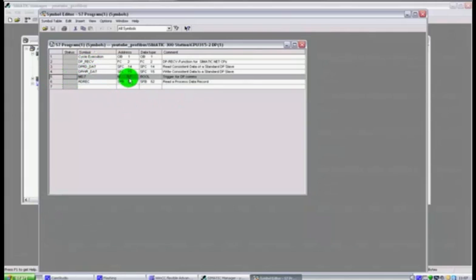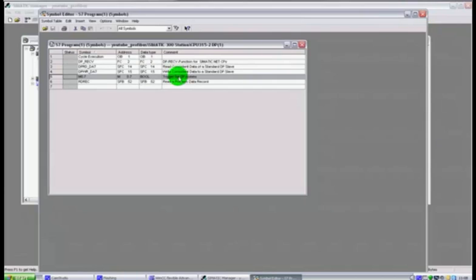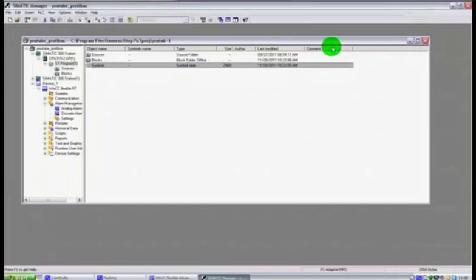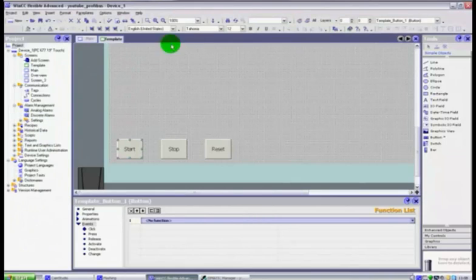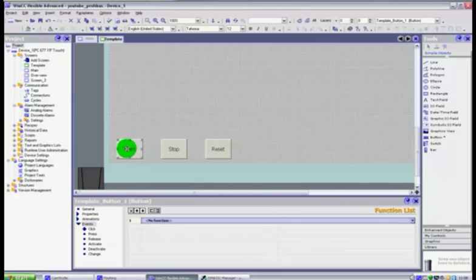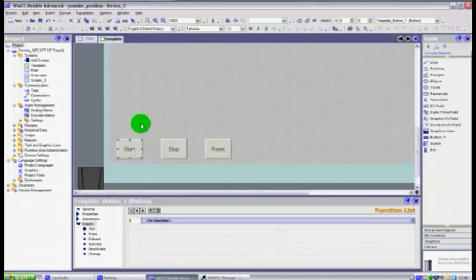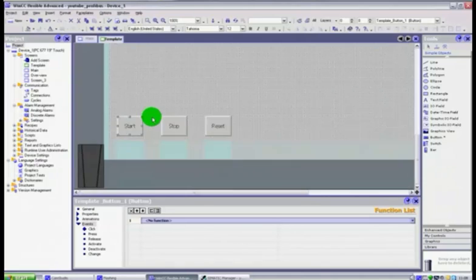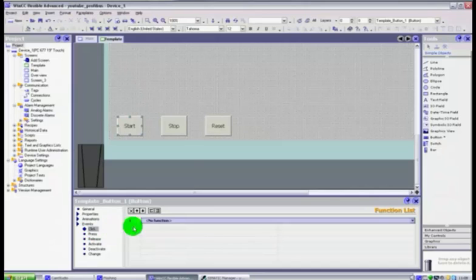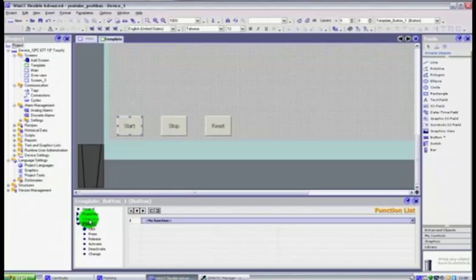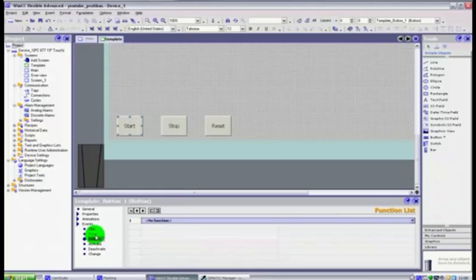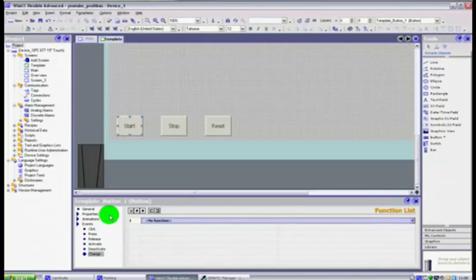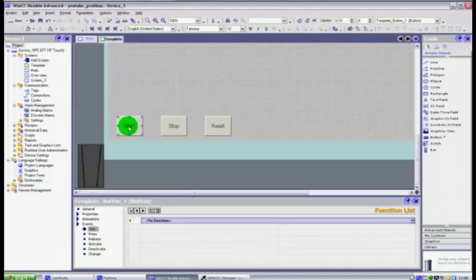The main one I'm looking at here is this one which is just a flag. We've got a name for it, an address and a symbol. Now the useful thing is that when we press this button I want that flag M0.7 to go high, and when I take my finger off the button I want it to go low. Now we could use the click command here. If you select the button under the events tag you get opened up all of these different properties - click, press, release, activate, deactivate or change.